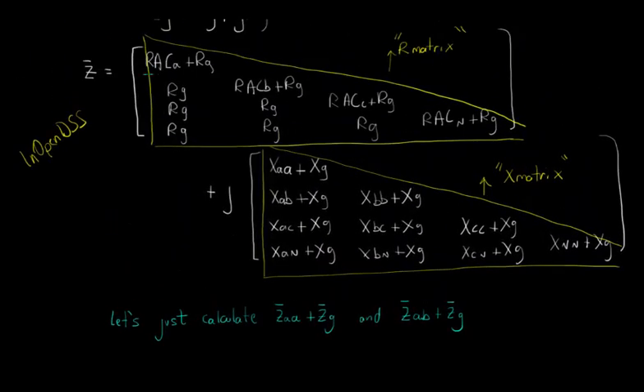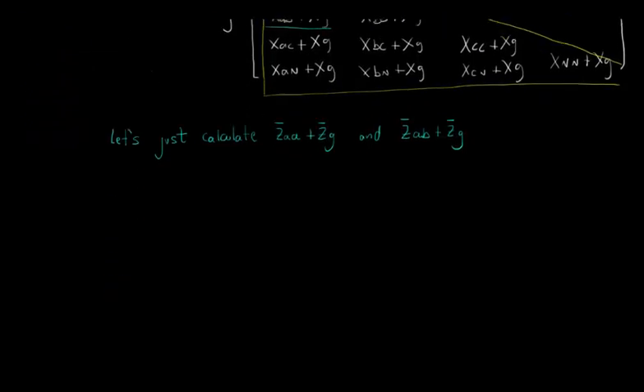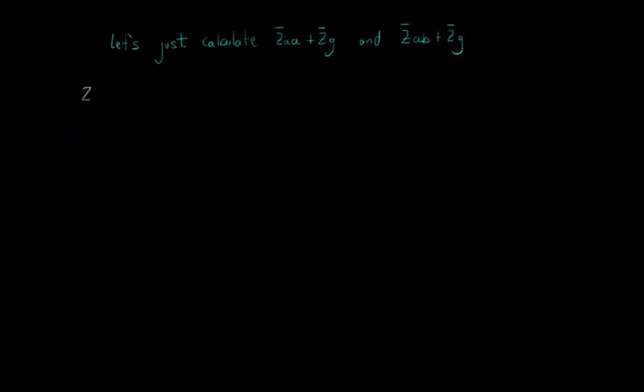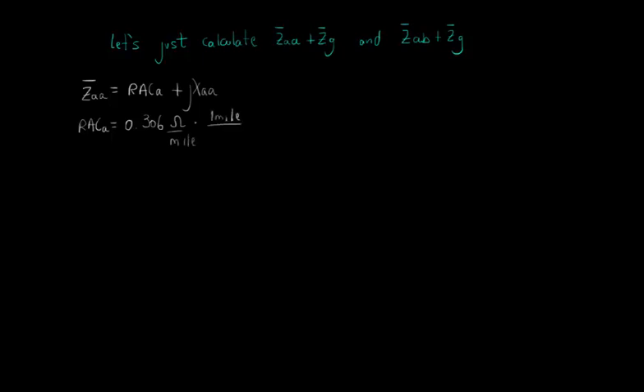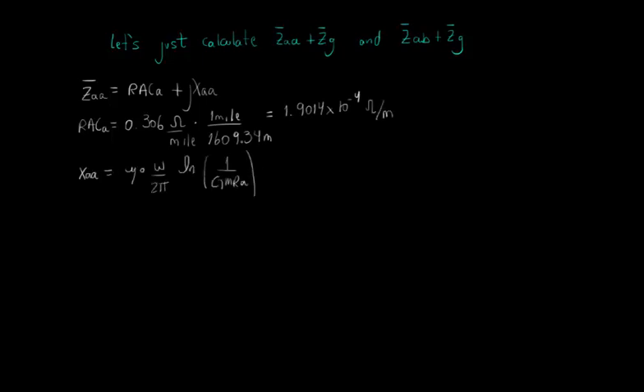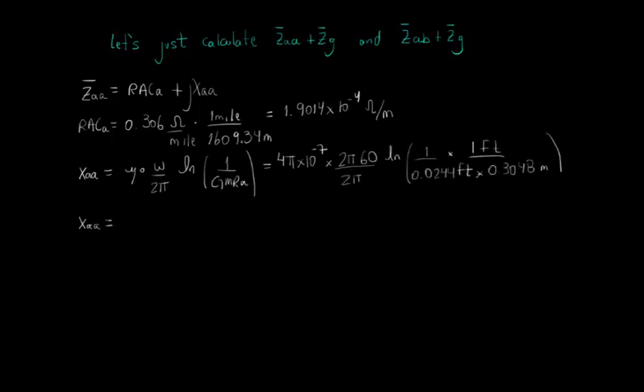using the equations that we have shown before and compare with the OpenDSS results. We know that ZAA is equal to the AC resistance plus XAA reactance. We've got from the table that RAC is equal to 0.306 ohms per mile. However, remember that the expressions that we will use to calculate the reactance are defined for distance units in meters. So, we have to convert this resistance from ohms per mile to ohms per meter.